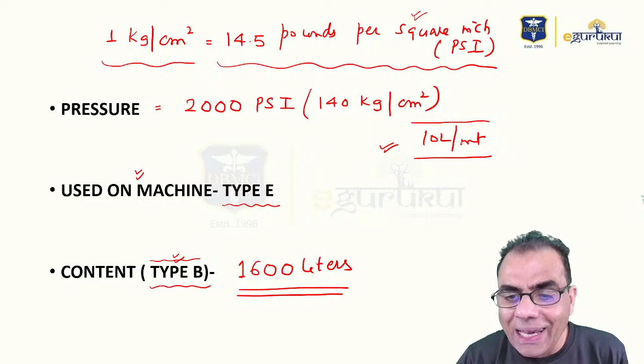1600 liters of oxygen. So nowadays the question they ask is, if you are giving, say, 10 liters of oxygen per minute to the patient, how long is your cylinder going to last? So 10 liters per minute means in 1 hour how much? 10 liters multiplied by 60 means 600 liters we are using in 1 hour. So a full cylinder is going to last how long if you are using 600 liters per hour? 600, 1200, 1500. So around 2 hours 40 minutes, something like that. You can say around 2.5 hours.